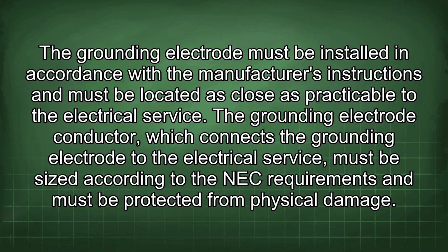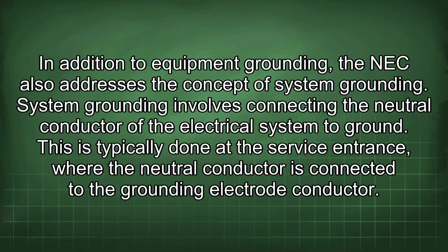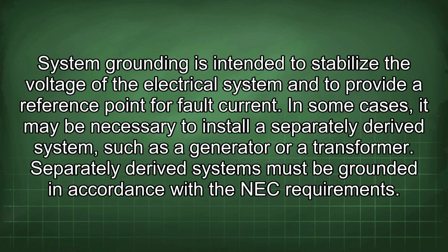The grounding electrode conductor, which connects the grounding electrode to the electrical service, must be sized according to the NEC requirements and must be protected from physical damage. In addition to equipment grounding, the NEC also addresses the concept of system grounding. System grounding involves connecting the neutral conductor of the electrical system to ground. This is typically done at the service entrance, where the neutral conductor is connected to the grounding electrode conductor. System grounding is intended to stabilize the voltage of the electrical system and to provide a reference point for fault current.